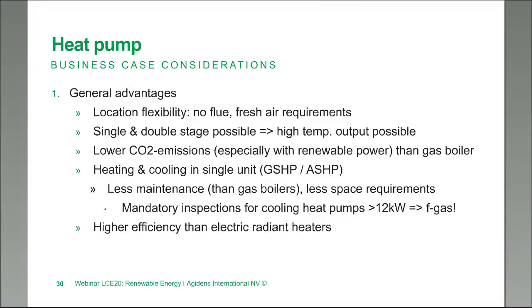You also have less maintenance than with gas boilers. Important to point out, however, is that if you're dealing with cooling heat pumps of more than 12 kilowatts, you will have mandatory inspections from time to time to make sure that none of the gases are leaking. The final advantage of heat pumps is the higher efficiency than electric radiant heaters. An electric radiant heater is more or less a one-to-one relationship in terms of COP, whereas with heat pumps you tend to work with COPs of probably three or higher.